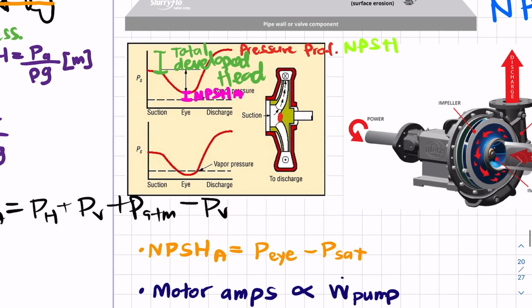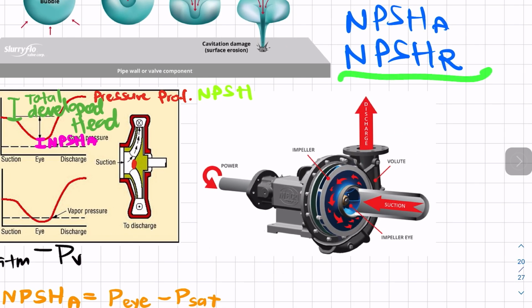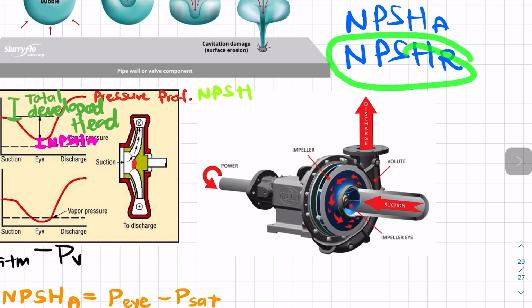So what is net positive suction head required? The net positive suction head required is just given by the manufacturer. They perform different tests on the pumps and determine the net positive suction head required. It's basically a measure of the minimum absolute pressure required at the suction side of the pump to prevent cavitation. So it's basically telling us, oh, net positive suction head required is this, right? It's just this part right here, the minimum that you need to avoid cavitation.